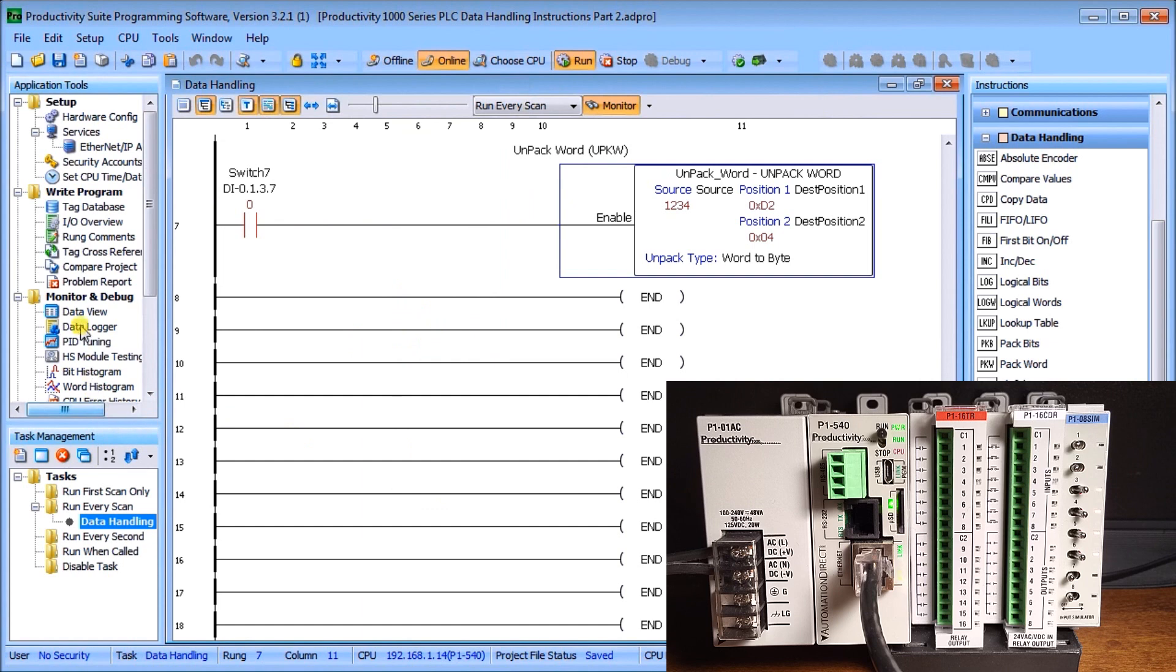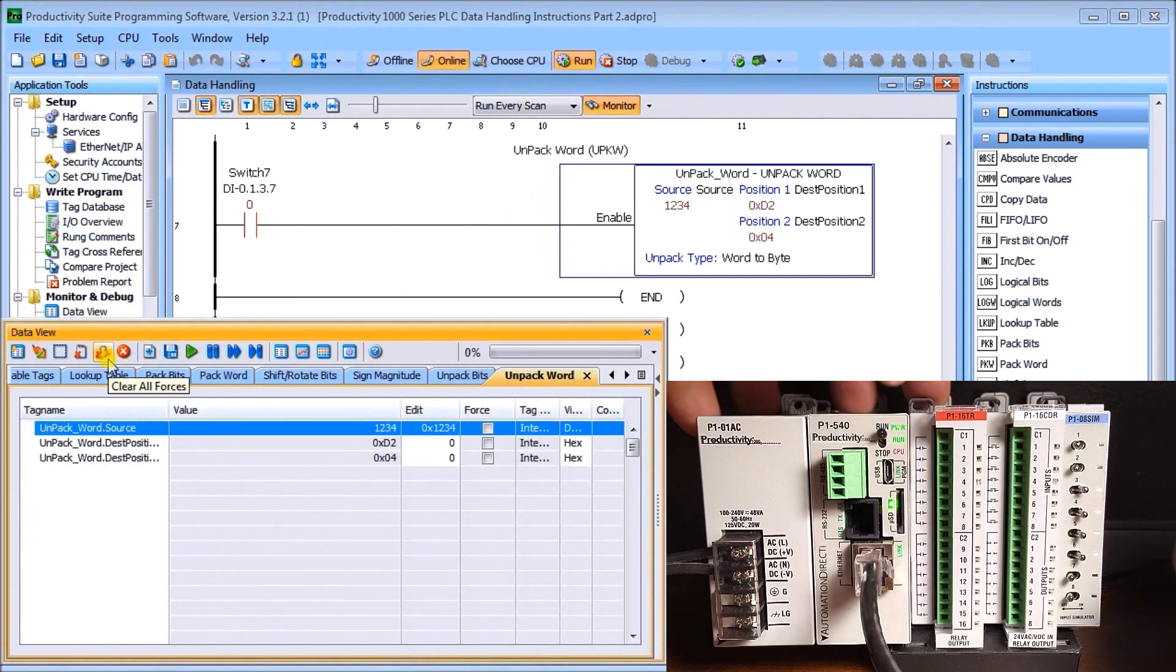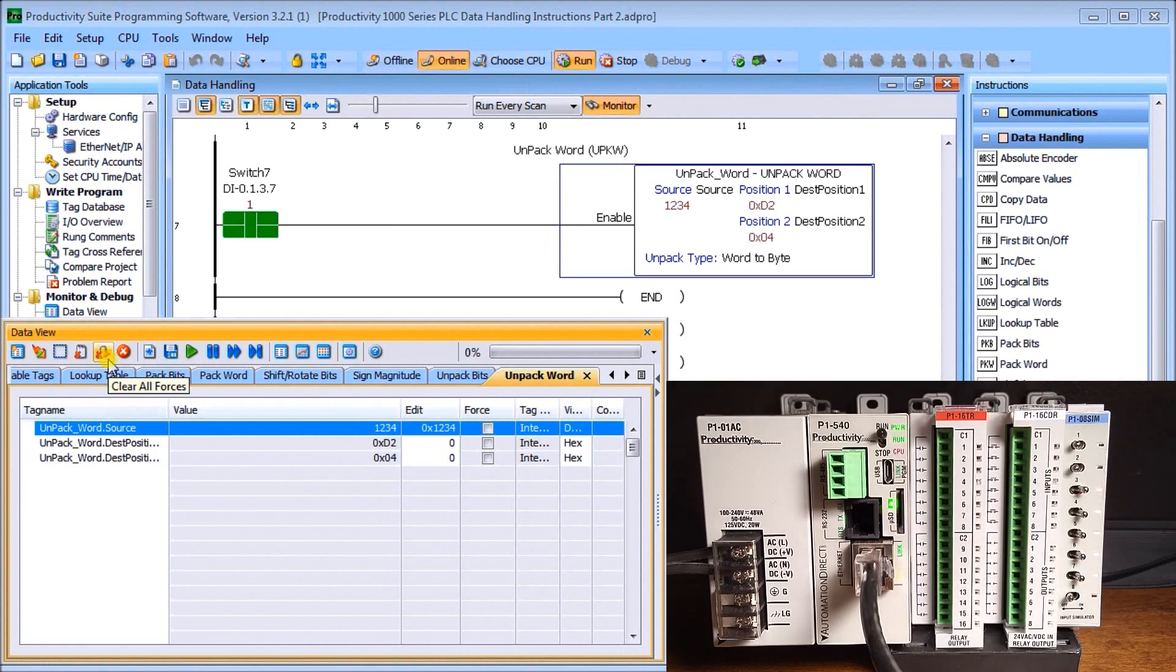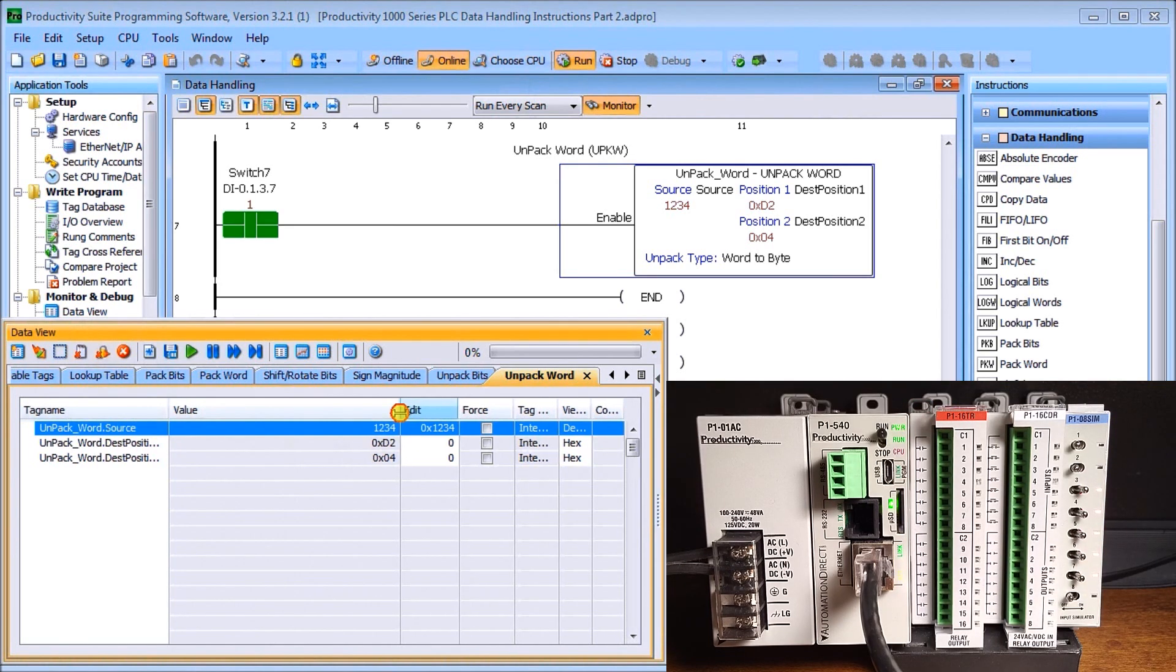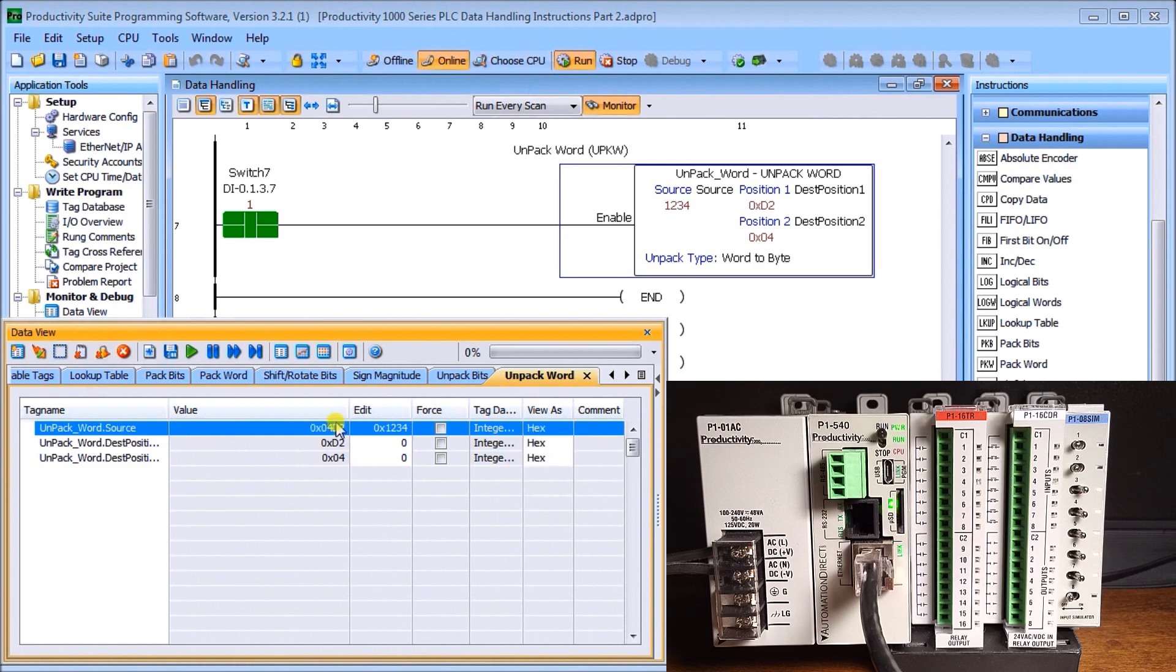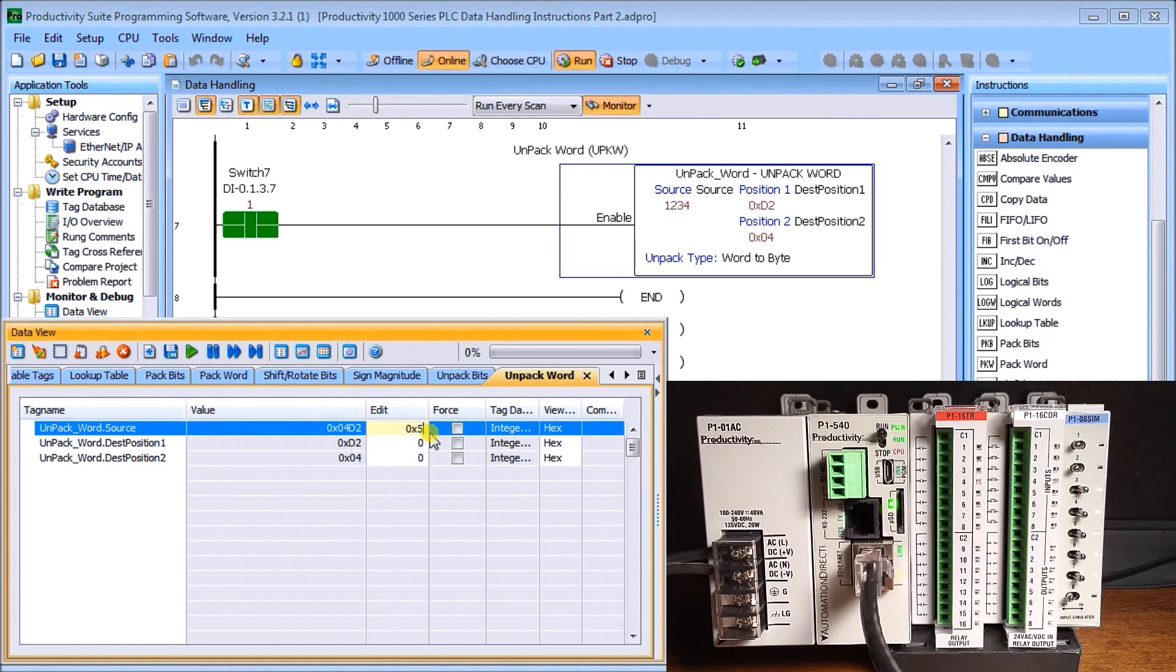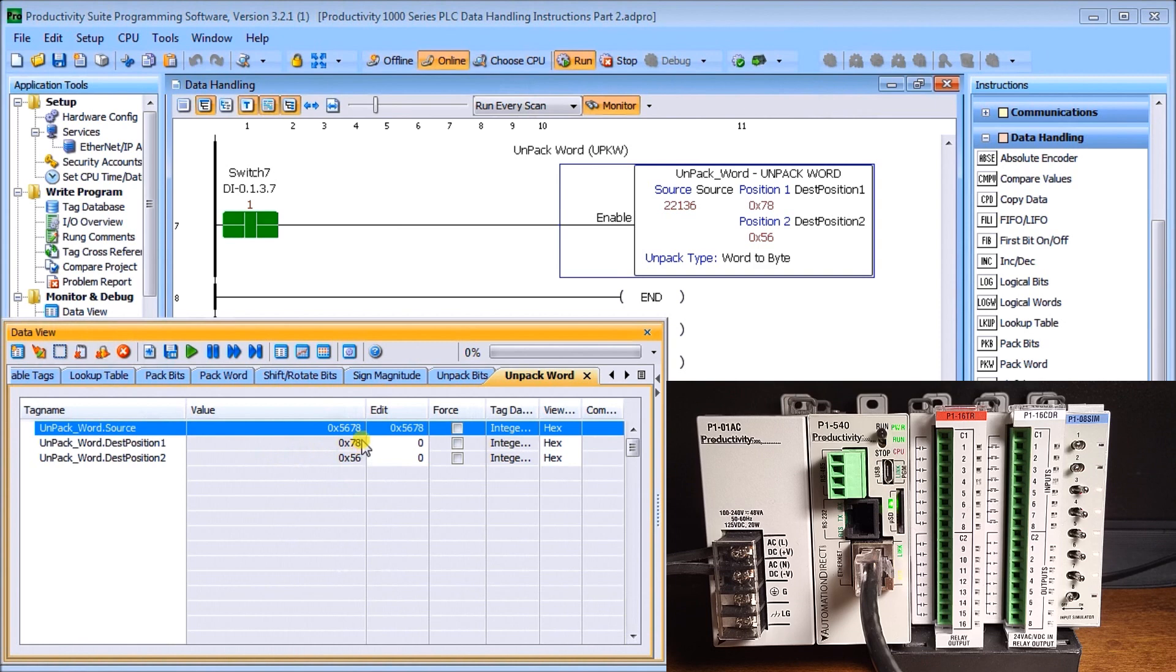We'll take a look at that data view and turn on switch number seven. We'll change our source word into a hex value, which is 04D2. You can see how it's separating the D2 and the 04 into my two unpacked destination locations. If I change this source word and put in 5678, we'll write that in. You'll see now my least significant byte is 78, which is in my first location, and 56 is my most significant, which is in my word destination position two.